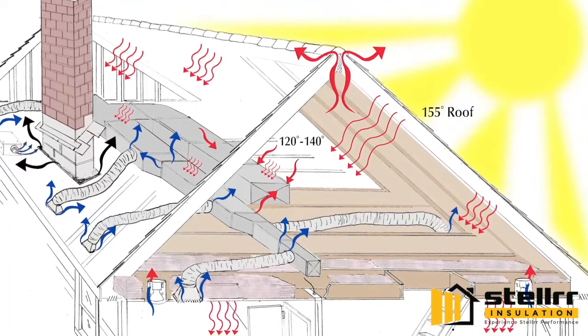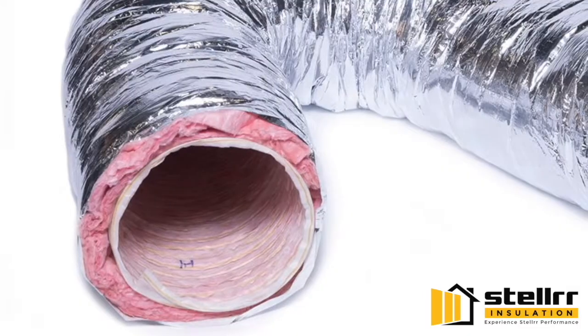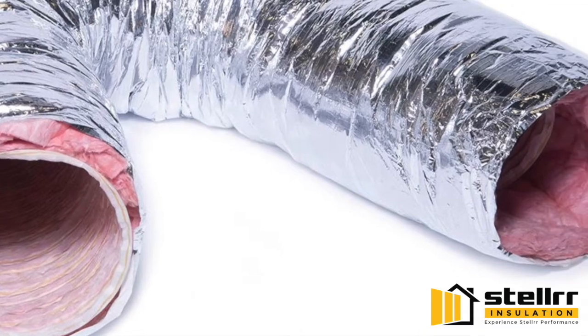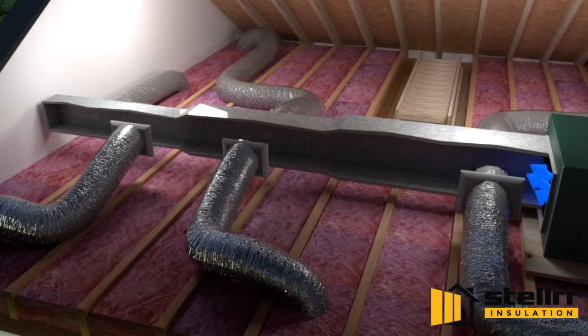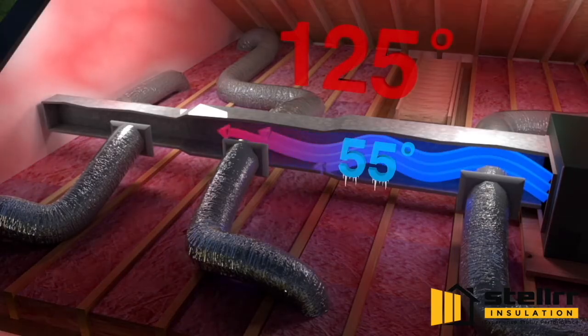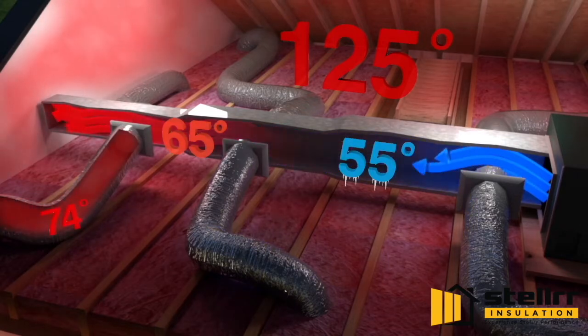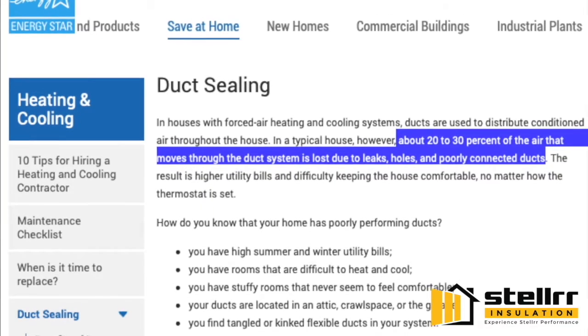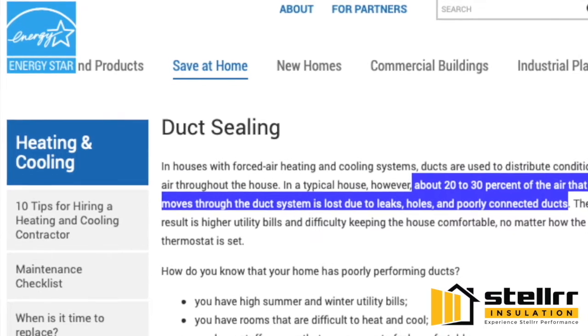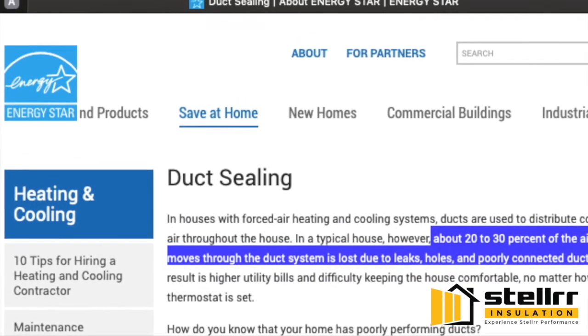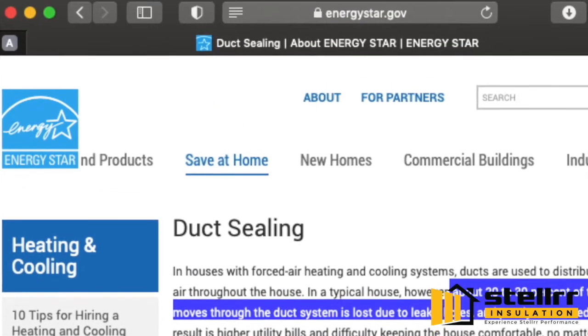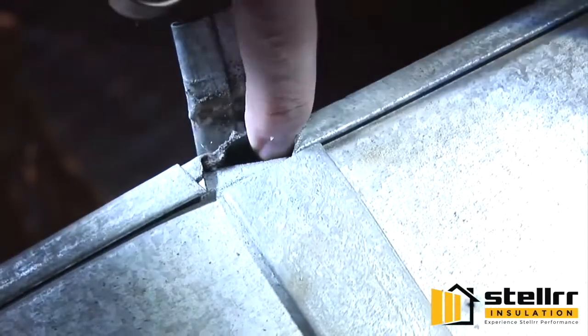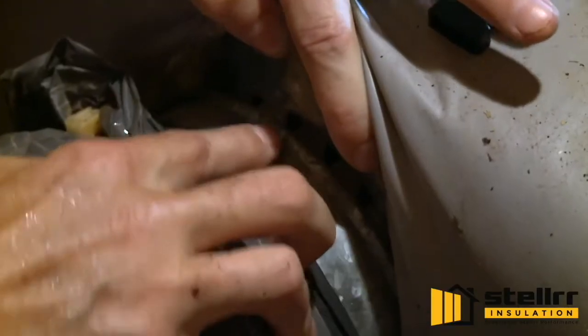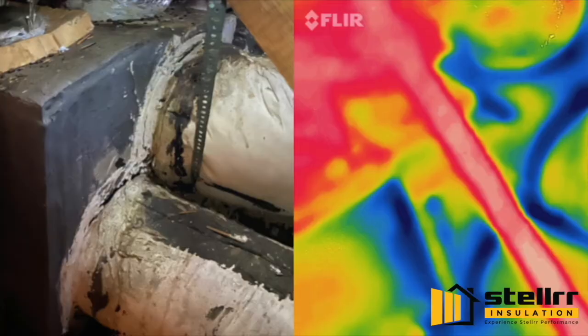Will replacing your ductwork with better insulated ducts fix the problem? No. They will still be reheating lines, as I like to call them, in the cooling season. Here's why. According to the U.S. Department of Energy, the average house air duct leakage is 30%, meaning 30 cents out of every dollar that's spent to condition the house is lost, wasted.